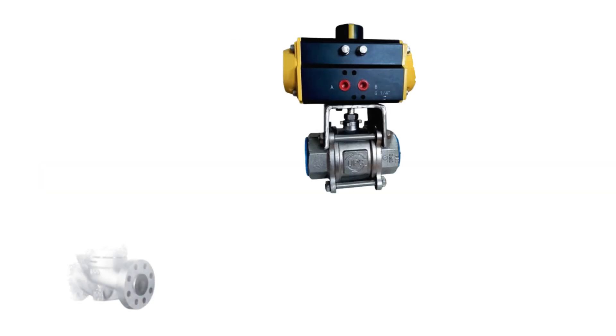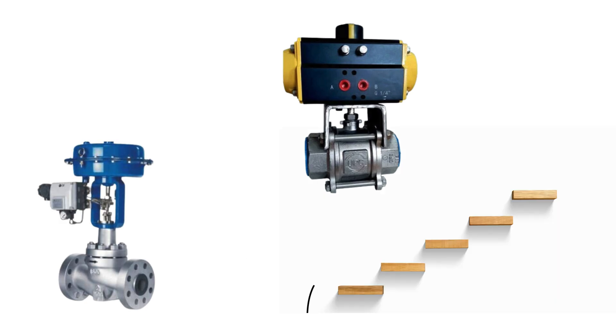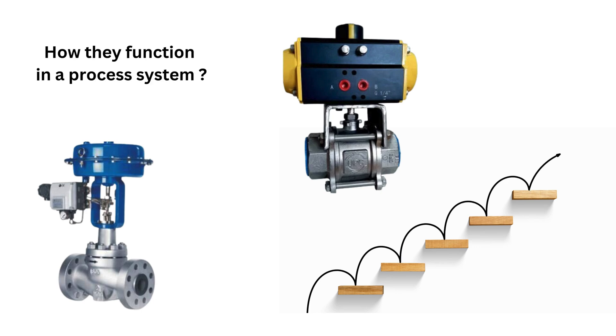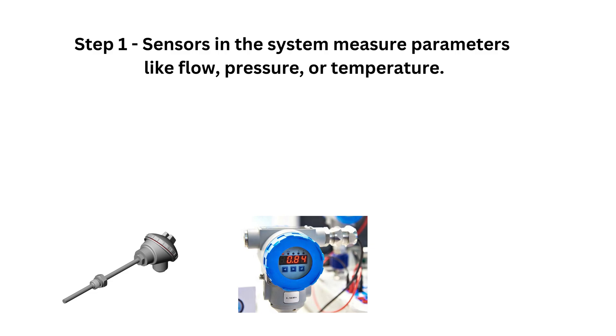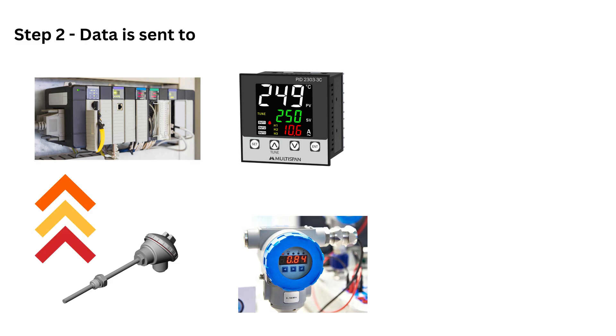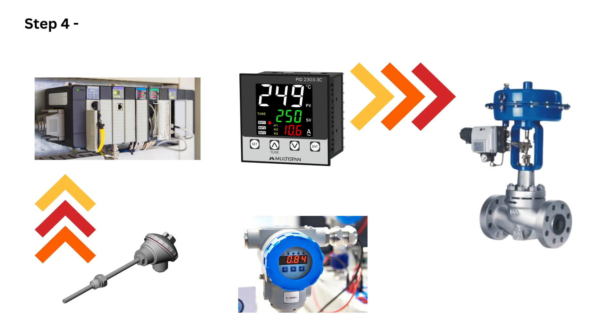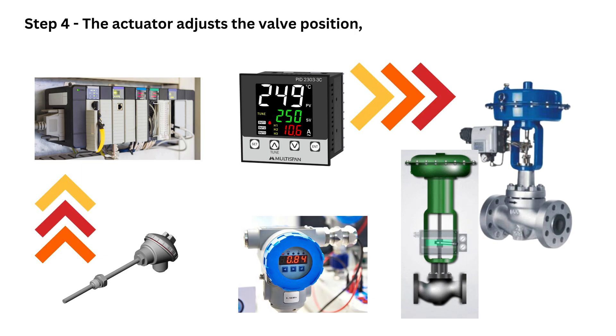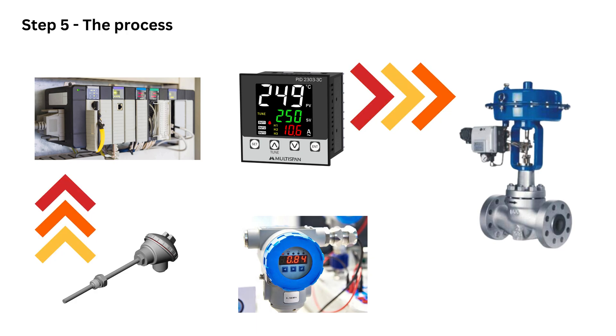Now we will discuss how control valves work in a system. Control valves are the final control element in a control loop. Here is a step-by-step breakdown of how they function. Step 1: sensors in the system measure parameters like flow, pressure, or temperature. Step 2: data is sent to the controller, which processes the information. Step 3: the controller sends a signal to the control valve's actuator. Step 4: the actuator adjusts the valve position, increasing or decreasing flow as needed. Step 5: the process stabilizes at the desired set point, ensuring optimal operation.